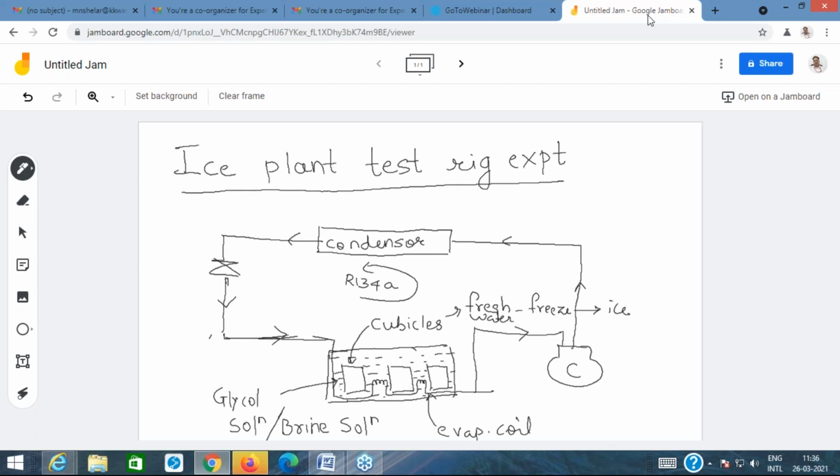The primary refrigerant is the one which participates in the actual cycle. That is, the primary refrigerant would flow through the compressor. It would get compressed up to the condenser pressure. It would be expanded in the expansion device, and then the primary refrigerant would absorb the heat in the evaporator. So that is the primary refrigerant.